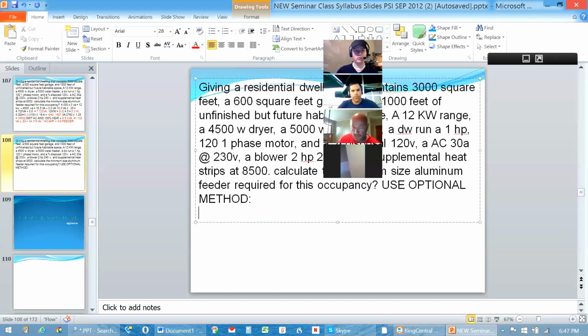I'm still taking the same 4,000 square feet, and I'm still going to take the 3 VA, so I still end up with the same 12,000 that I had on the standard method. Then under Part 2, I'm going to add the same 1,500 for each one of the 3 required 20 amp circuits, which are the 2 kitchen and the laundry. So I'm doing the same step here again, plus 4,500. That doesn't change either. That gives me the same 16.5 kVA that I had in the standard method. The difference is that I don't derate it here. I'm just going to keep on trucking.